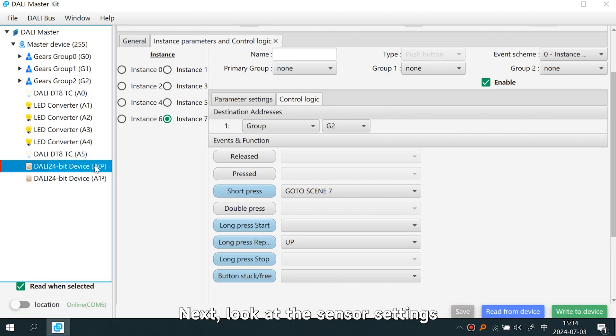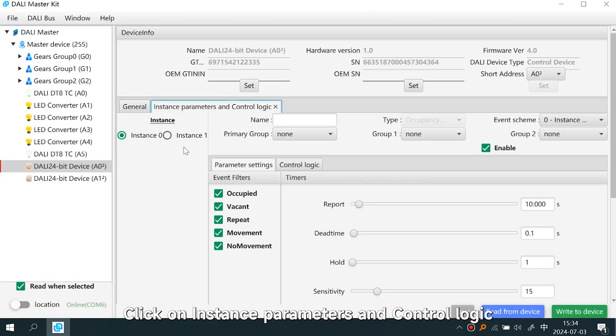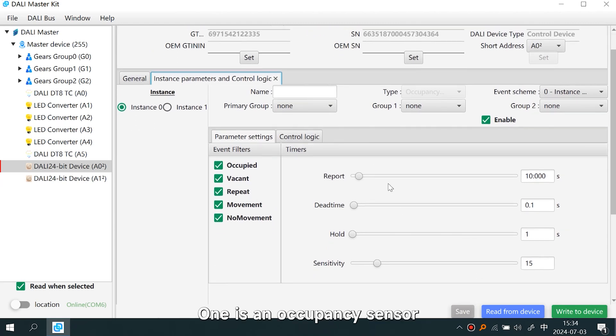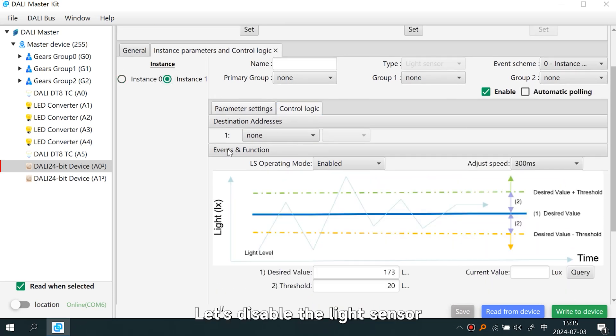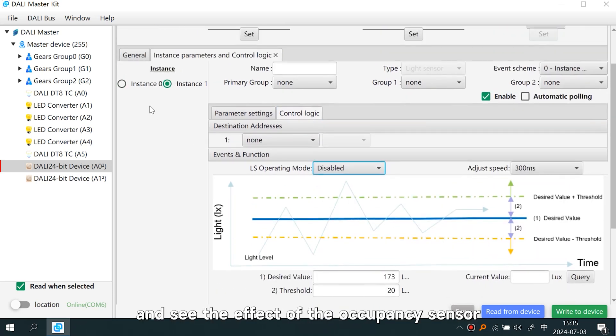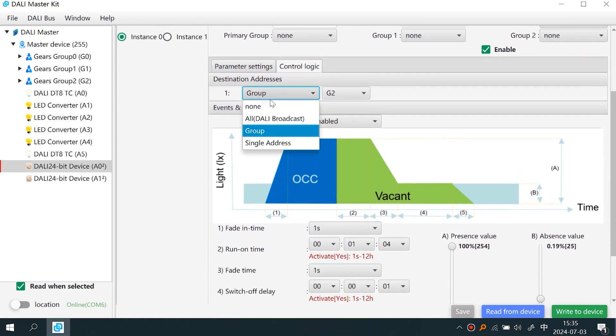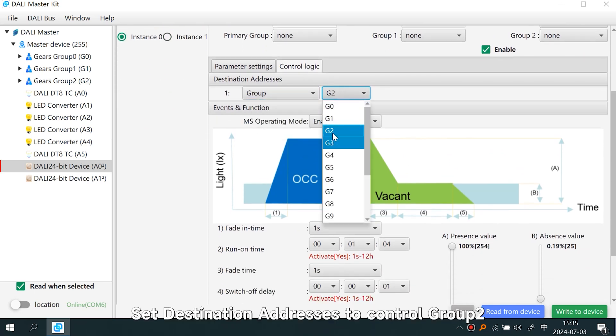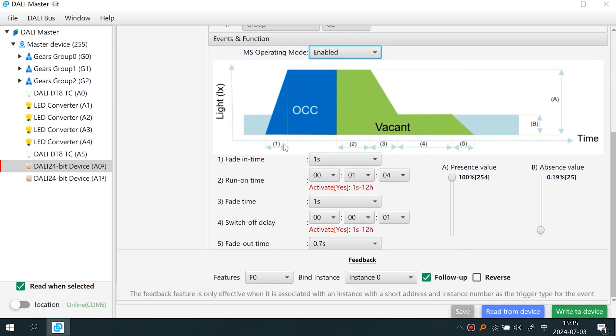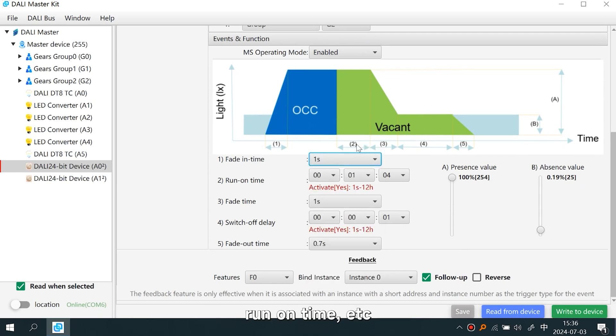Next, look at the sensor settings. Click on Instance Parameters and Control Logic. There are two instances for this sensor: one is an occupancy sensor and one is a light sensor. Let's disable the light sensor and observe the occupancy sensor. Click on Instance Zero, then click Control Logic. Set the destination address to control Group Two and enable it. Then set the timing parameters as desired, such as fade in time and run on time.